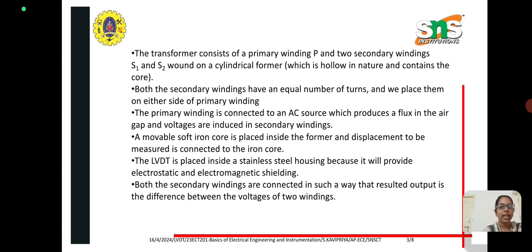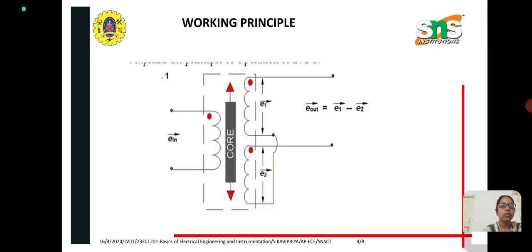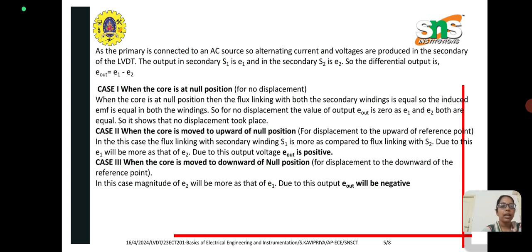Both the secondary windings are connected in such a way that the resultant output is the difference between the voltages of the two windings. Next is the working principle behind the LVDT. As the primary is connected to the AC source, alternating current and voltages are produced in the secondary of the LVDT. The output in secondary S1 is given by E1 and in secondary S2 is given by E2. So the differential output is E1 minus E2.